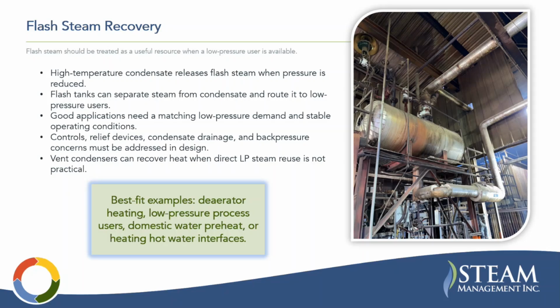If you can take that to a pressurized condensate tank and let it flash at, say, 10 pounds, and then capture that steam and reuse that in a low pressure steam system, now the condensate coming out of that flash tank is now only going from 10 to atmospheric, and there can be a significant reduction in flash steam losses, which is going to improve your condensate return as well. And there's a good savings benefit.